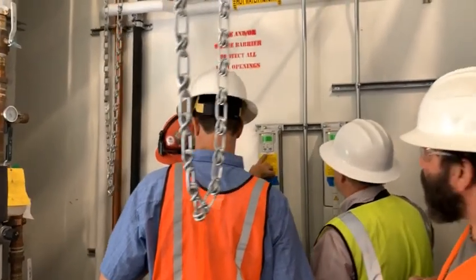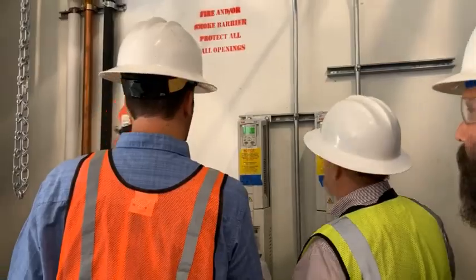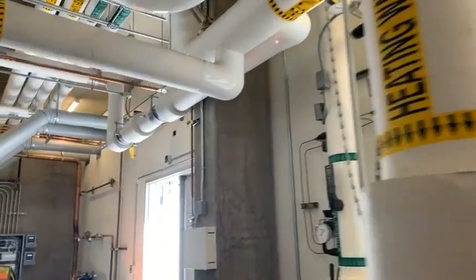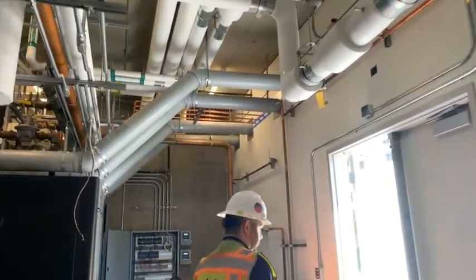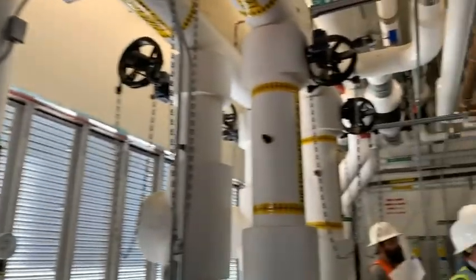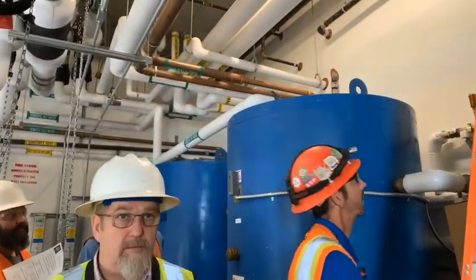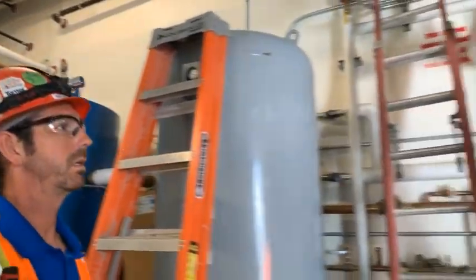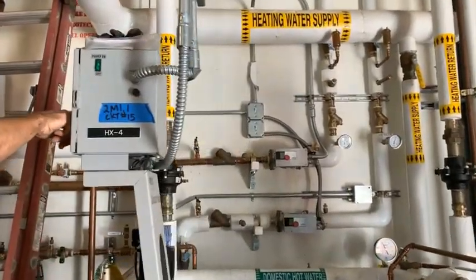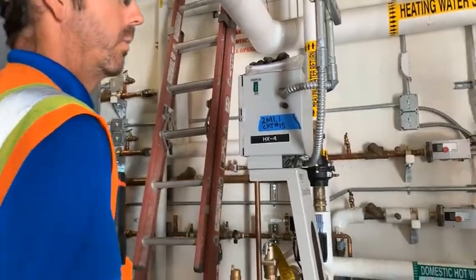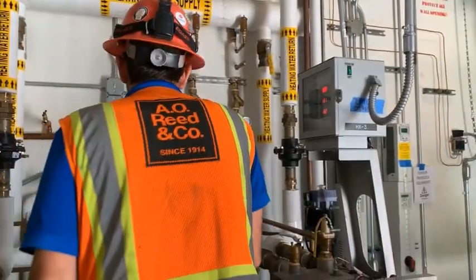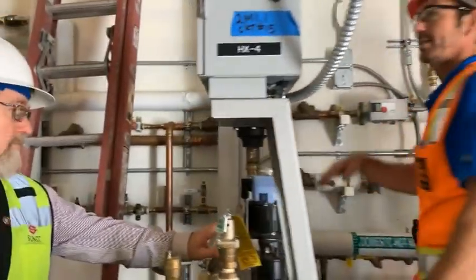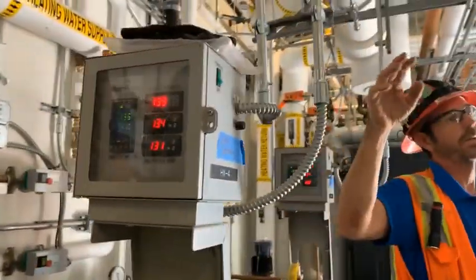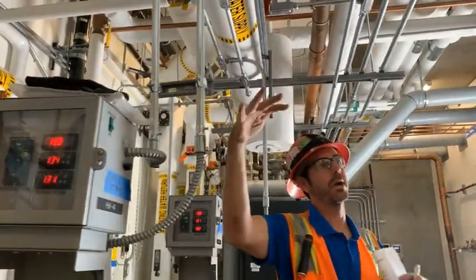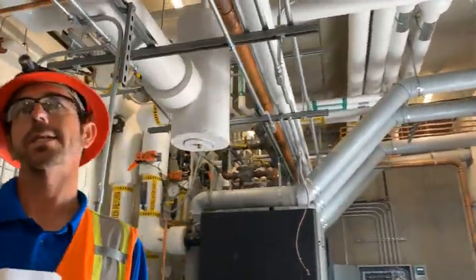Let's go though, because it's quiet. Chilled water pump, chilled water pump. We don't necessarily care about those right now, and we see our buddy sitting in the corner over there. These are our tank circ pumps. So we got 135. We'll do training on this. We got 135. Because if our tanks aren't at 140 either, we're relying on that 140 going into the mixing valve. So if we start dropping that tank temp, then we won't be able to mix to that 120 outlet temp.